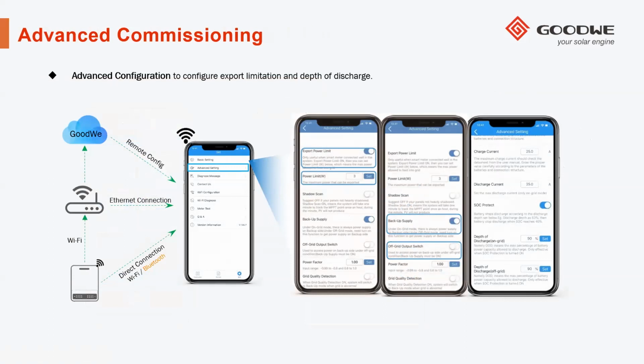So our advanced configuration. On the application, we have advanced configuration. In advanced configuration, we've got export power limit, and that needs to be put on for most places in South Africa and Africa. If the utility allows you to feed back, you can disable that. If they only allow you to feed back a certain amount, you can put in the amount of feedback you'd like here and press set. For zero export, it would be recommended to set 0. We are working on having this set negatively, and that should be released in a few months' time.